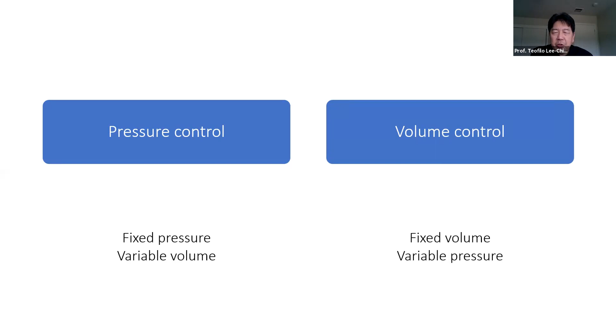So what's a therapy? When we talk about ventilation, whether it be invasive or non-invasive, there are two types of devices, a pressure control and a volume control. A pressure control is any device that's designed to provide a fixed pressure with every breath. However, because of differences in lung compliance and airway resistance, the volume delivered is variable and often unpredictable. In contrast, in volume control, the device is designed to provide a fixed volume. But for the same reasons of changes in compliance and airway resistance, the pressure is variable.